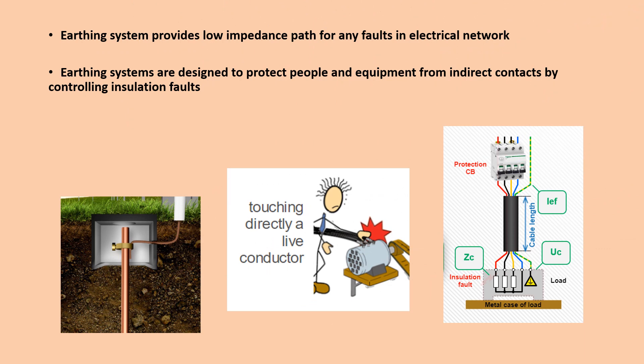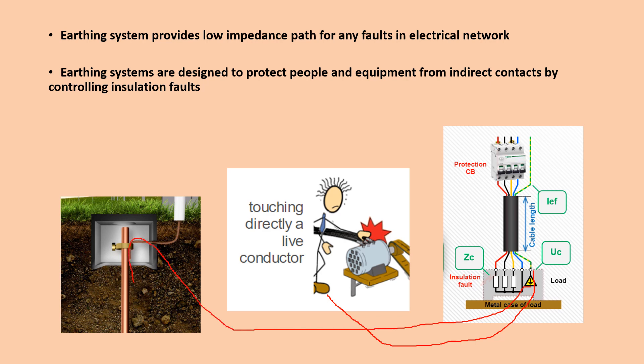Here is a beautiful property: current always flows in a low-resistance path. By providing earthing, what happens is — the earth wire is connected to the equipment, whether it's a motor or a water heater. If a fault occurs, the DB will trip first. But if for some reason it does not trip, the fault current will flow through the earth rod instead of passing through you. The current will choose the low-resistance earth path, so you will not get any shock.